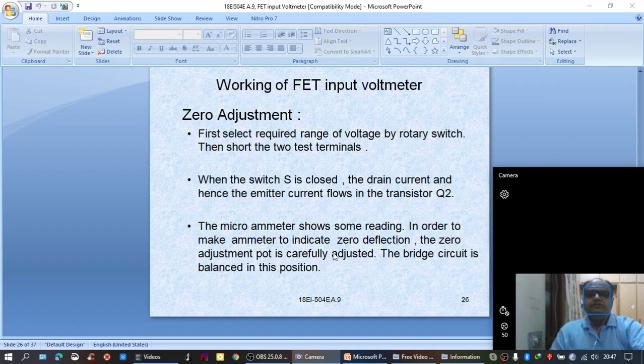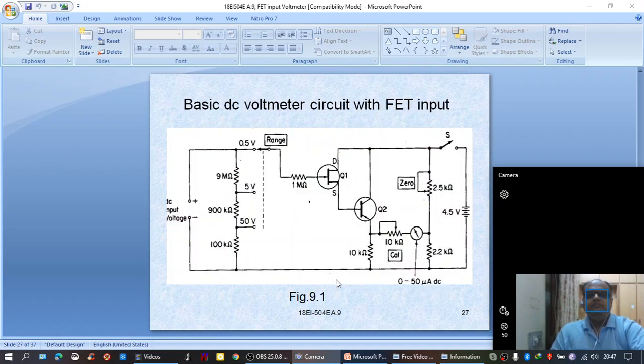In order to make the ammeter indicate zero deflection, the zero adjustment pot is carefully adjusted. The bridge circuit is set to be in balanced position when the meter reads zero. By adjusting this potentiometer, the bridge is brought to balance condition. That is, the potential at this terminal will be equal to the potential at this terminal. As a result, there won't be any potential difference across the microammeter. So naturally, no current flows through the meter and the pointer would be set to zero position. This is done by adjusting this pot, by connecting the switch to any one of the ranges and by short circuiting the input. That is called zero adjustment.